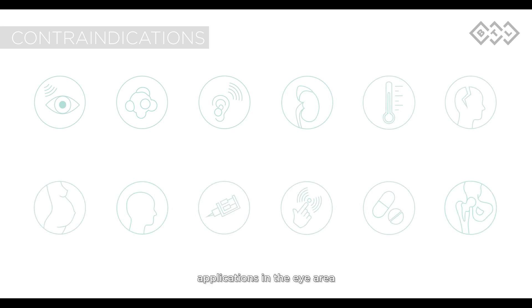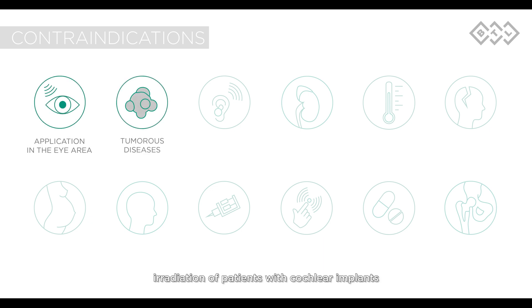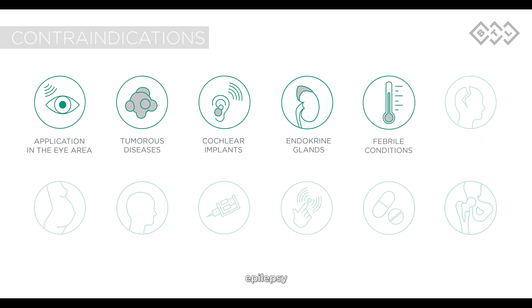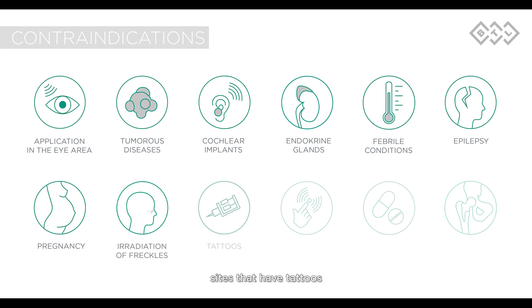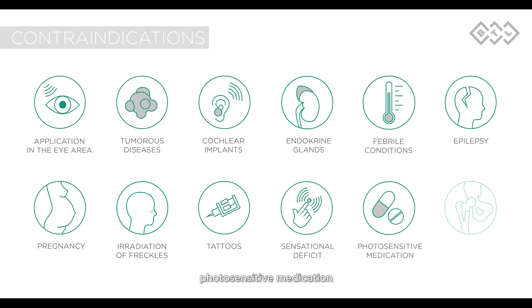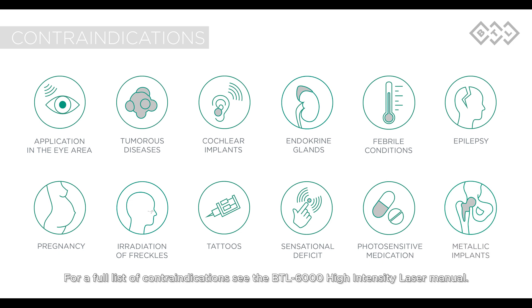Ask the patient about possible contraindications to the BTL high-intensity laser. The basic contraindications are: applications in the eye area, tumorous diseases, irradiation of patients with cochlear implants, irradiation of endocrine glands, patients with febrile conditions, epilepsy, pregnancy, irradiation of freckles, sites that have tattoos, sensory deficit, photosensitive medication, and application above metallic implants. For a full list of contraindications, see the BTL 6000 high-intensity laser manual.